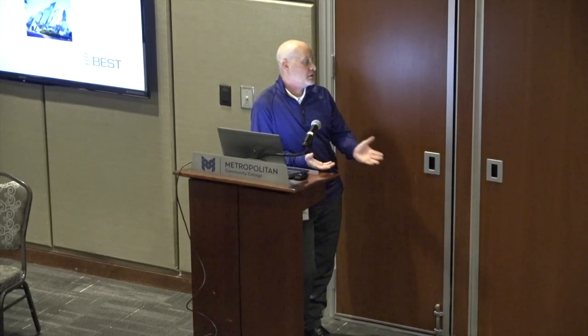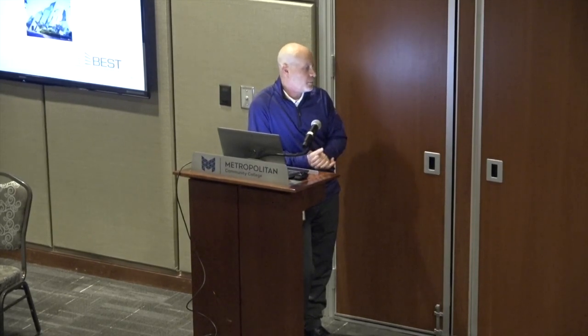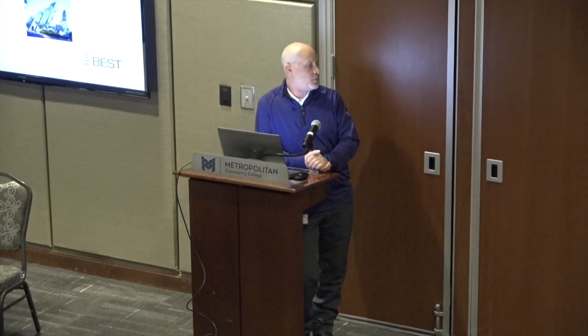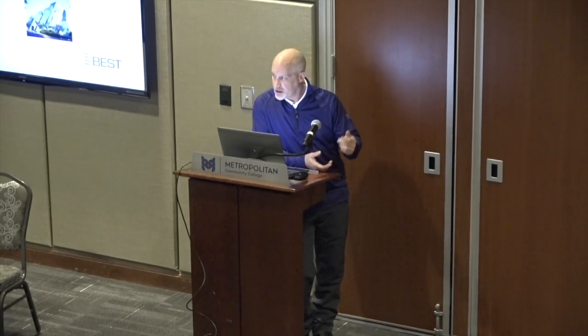Let's take a case, space comfort controller, for example. A heat pump could be a VAV. Our purpose is to make that space comfortable. At the bottom line, we give it a set point, let's say 70 degrees, and we want it to stay there. We also want to provide ventilation for that room. Now this particular room here, it's sized for all of us, however many people are here breathing, ventilation from outside is coming into this room.